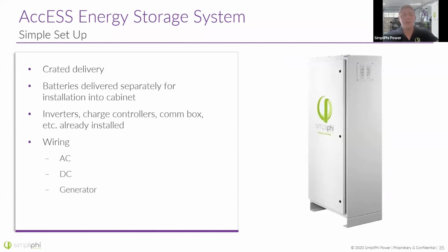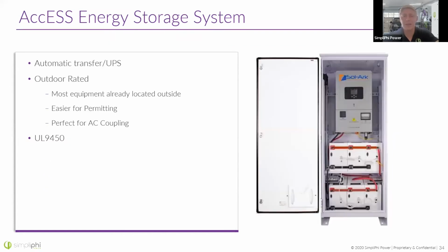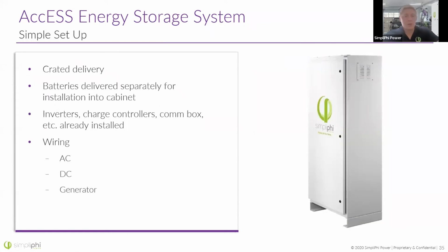These units are going to come with a crated delivery. So just rewinding here a bit, the inverter is going to be pre-mounted and pre-wired in the cabinet with the connections hanging loose. And the batteries are going to be sent separately in boxes. So you will have to make those DC connections with the batteries because we want to keep them safe during shipping. But the bus bars are mounted, the inverter's got those wire connections made internally, and the DC connections made. You just need to finish them up. Whether you are AC coupling or DC coupling, or even adding a generator to either of those scenarios, our units are going to have all these connections already built in.